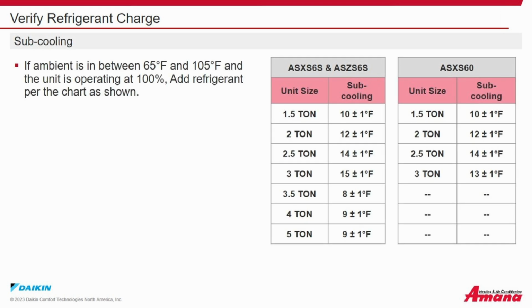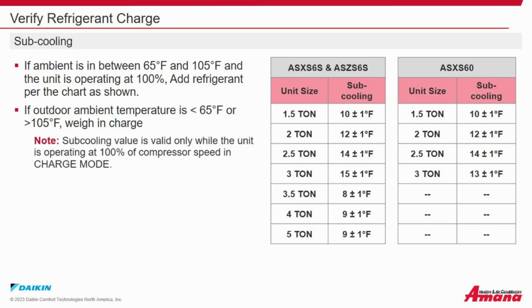Verify refrigerant charge. Subcooling. If the ambient temperature is between 65 and 105 degrees Fahrenheit and the unit is operating in 100% capacity, add refrigerant per the chart as shown. If the outdoor ambient temperature is less than 65 or greater than 105 Fahrenheit, weigh in the charge. Note: subcooling value is only valid while unit is operating in 100% of compressor speed in charge mode. Subcooling value displays on the 7-segment display only during the charge mode.